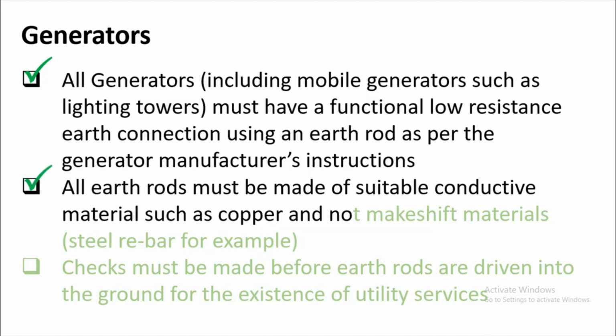All earth rods must be made of suitable conductive materials such as copper, and not makeshift materials, steel bar or steel rebar, for example. So the earth rods should only be made of copper. Steel bar is not allowed as earth rods. Okay?